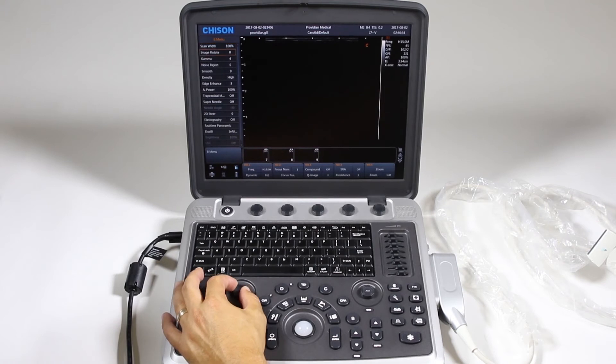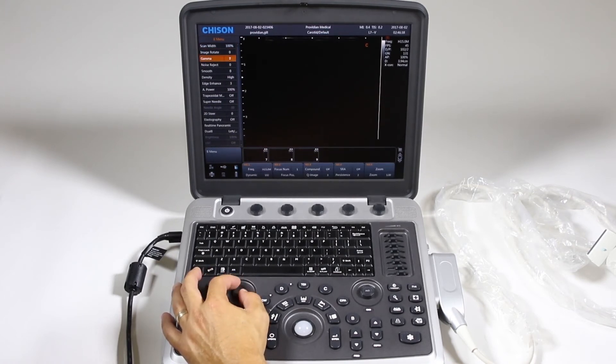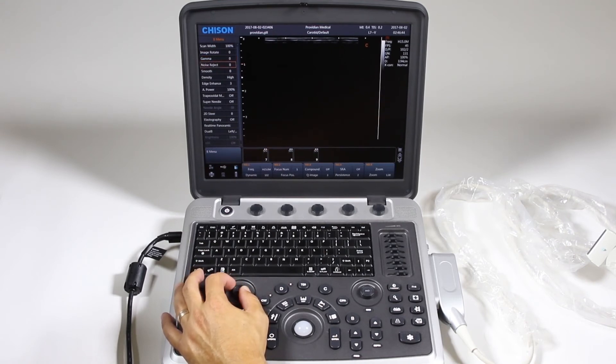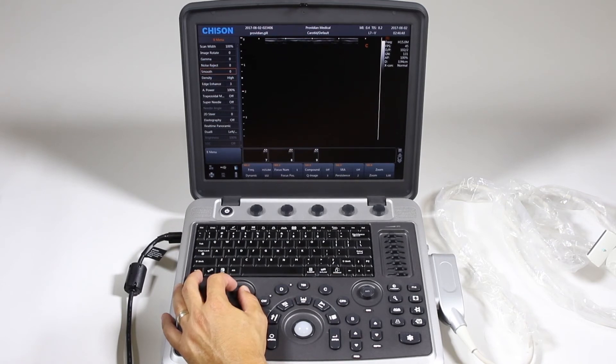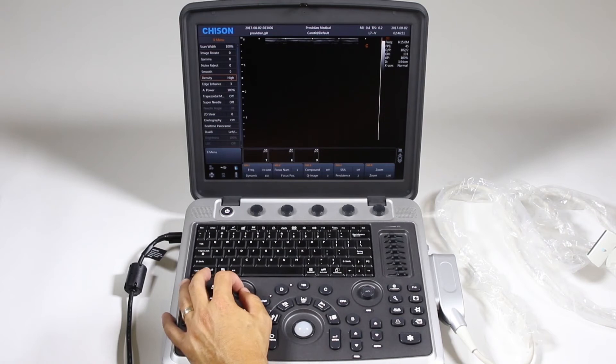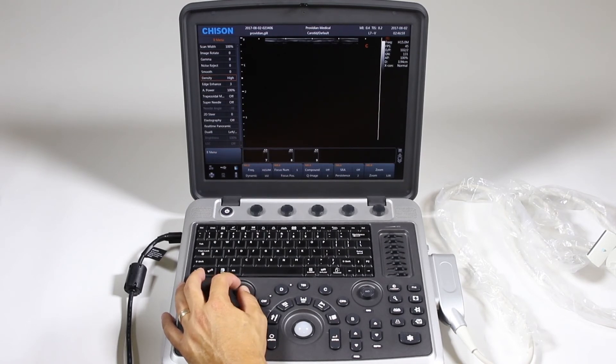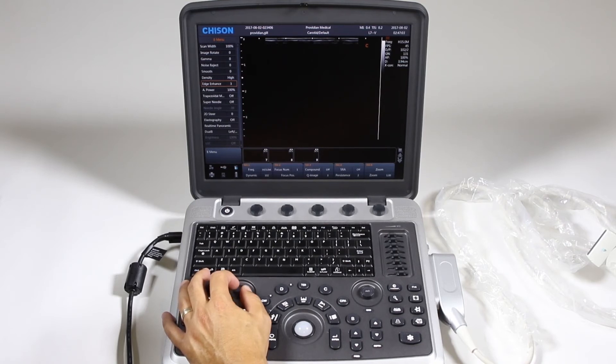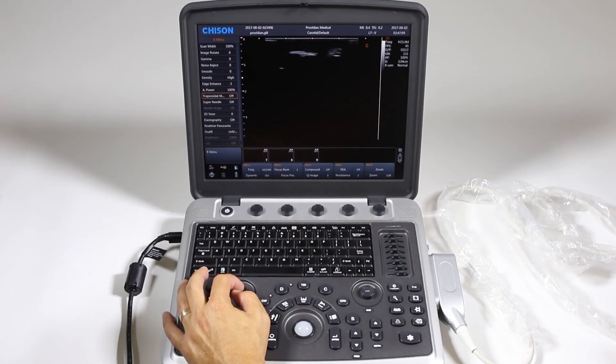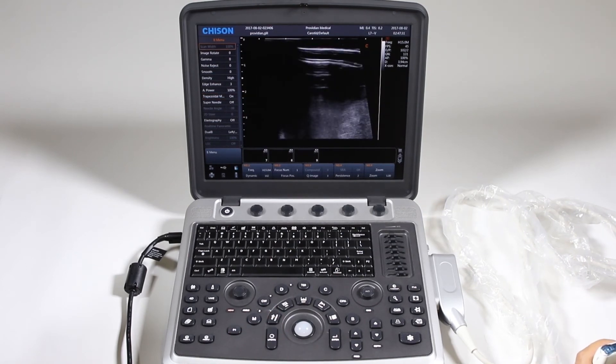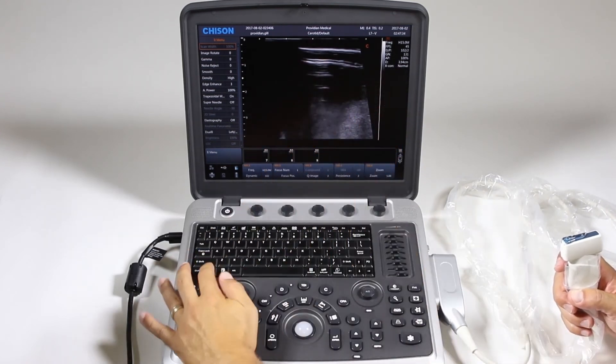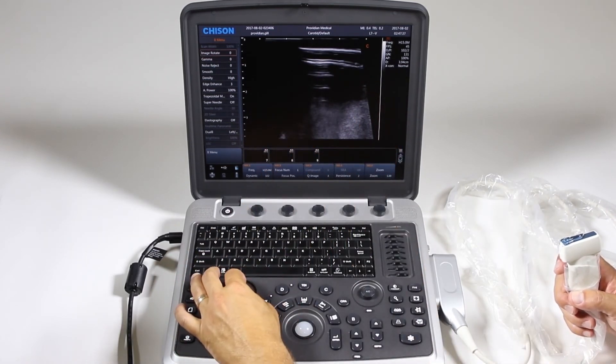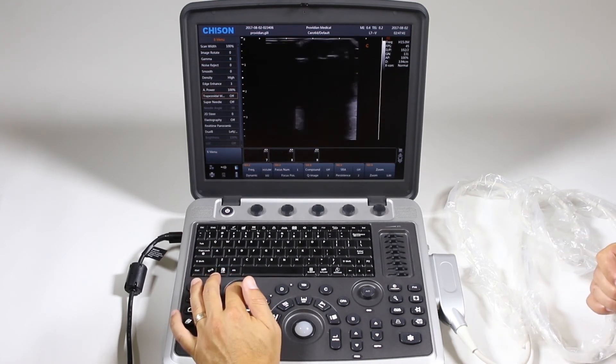Okay, back to over here. My gamma, that changes the overall brightness in an image. You can turn that down or up. Noise rejection, again this is just try to get rid of artifact. A lot of these are just image optimization, image smoothing, line density. Typically you'll want that as high. If you have a low line density, typically what you're trying to do is get a high frame rate. This machine generally has really high frame rates. You probably won't need to adjust your line density unless in some mode it says low. You should try the high edge enhancement, acoustic power. Trapezoidal mode, if you turn that on, you can see how trapezoidal mode gives your image a trapezoid. Scroll back down, on and off, so you can get a wider angle deeper in the image.